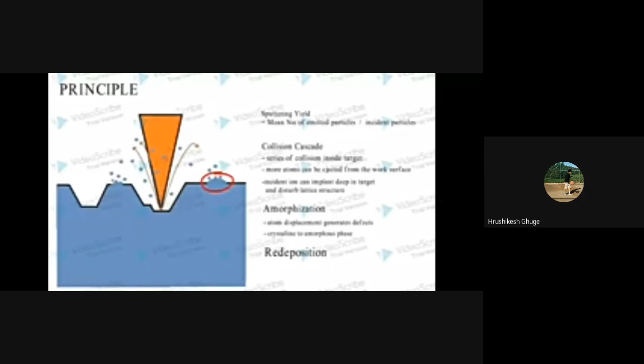As this whole process is occurring in a vacuum, the atoms removed by the sputtering process sometimes cannot be evacuated by the vacuum system. They can get deposited on the adjacent surface where the milling is going on. The redeposited material sometimes settles on the side and other surfaces. That will lead to sputtering a second time, which obviously increases your process time and effort. So redeposition is surely an undesirable phenomenon in focused ion beam machining. Redeposition is observed highly when there are holes or trenches or narrow slots, where the redeposited material is also difficult to evacuate.